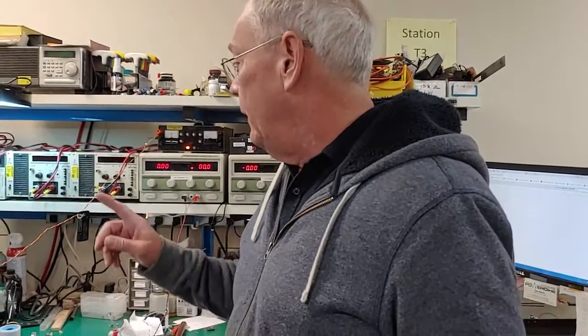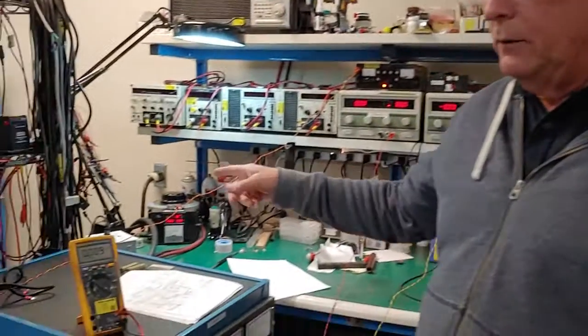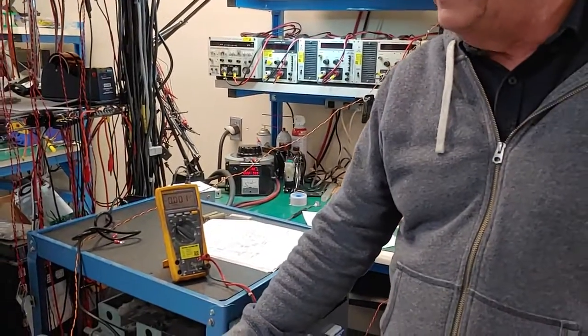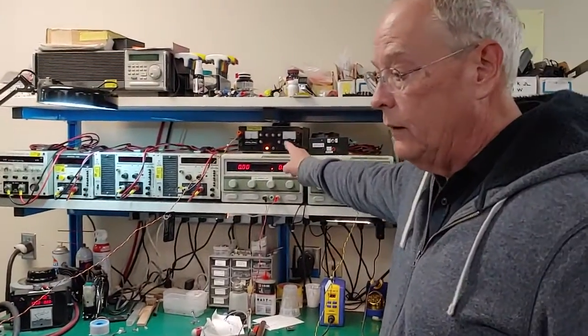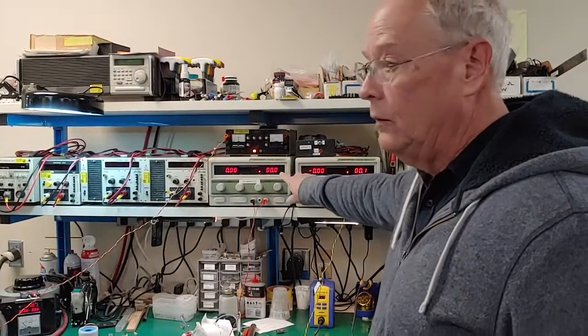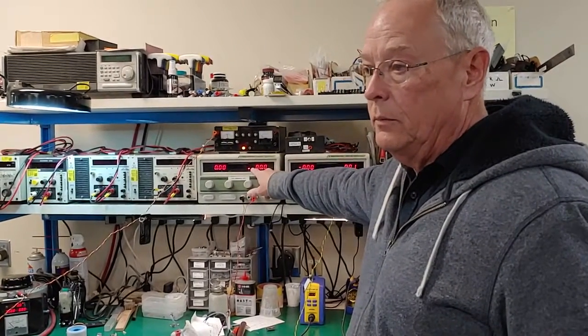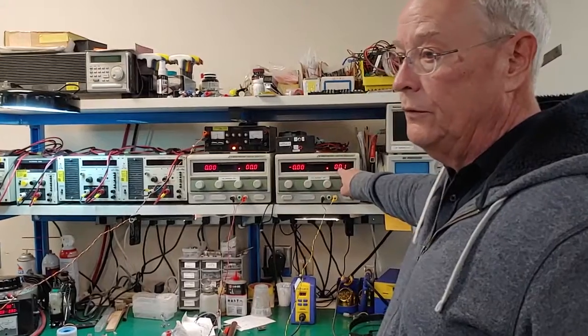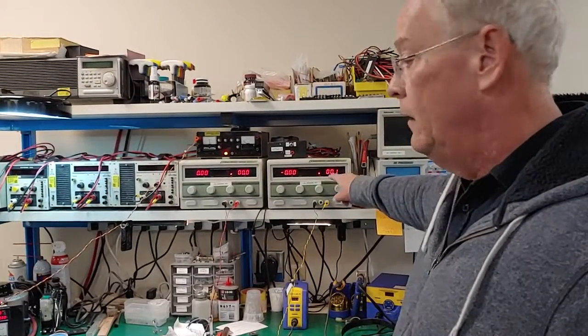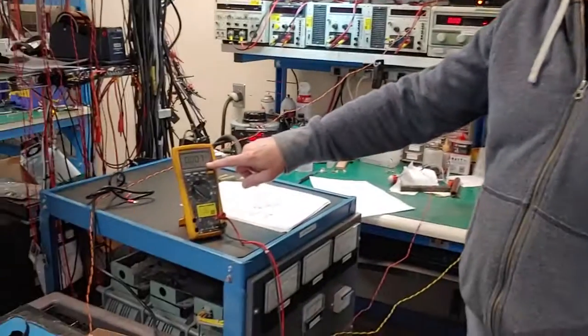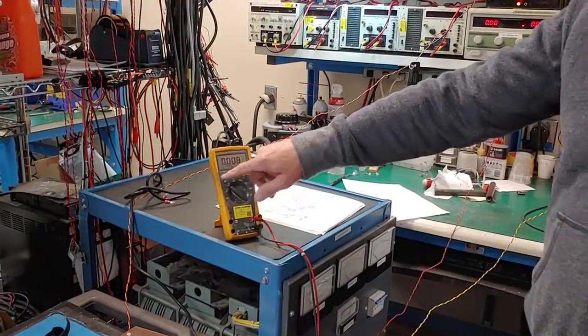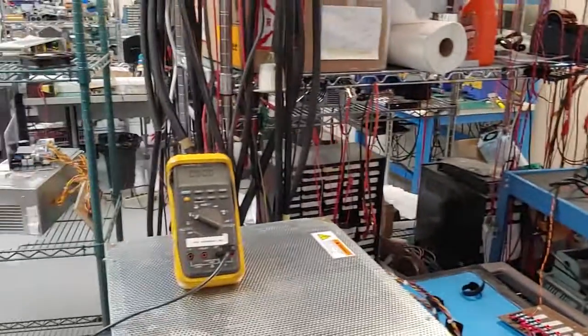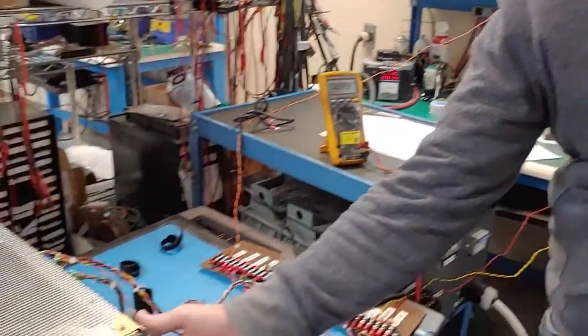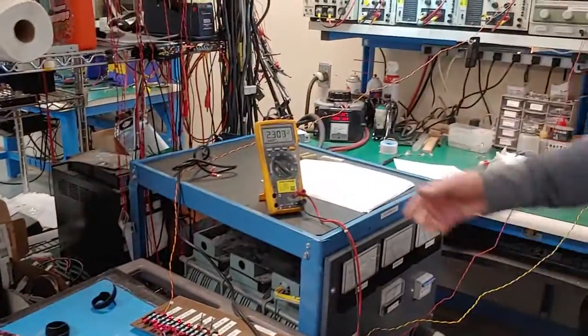So, anyway, we've got a voltage applied to our filament selection switch. We've turned it on. First thing we do, make sure that we've got 12 here for our auxiliaries. We've got 2 controls. 6 volts will equal 60,000 volts. 4 volts here will equal 40 mils. First thing we're going to do is monitor the filaments, make sure it comes up, and I should be at 0 high voltage. So everything's applied except just throwing the breakers. We'll go ahead and turn the breakers on. All right, here we go.